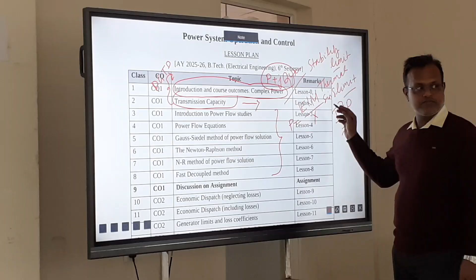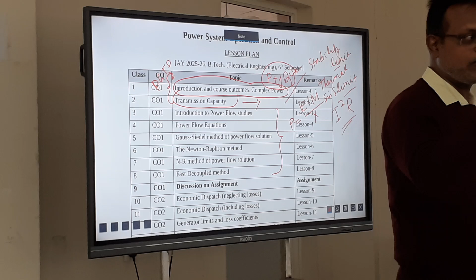Okay. So for a transmission line, it will be V1 V2 by X sin delta. So delta can be at most 90 degrees. So in that case, the transmission capacity of a transmission line is simply V1 V2 by X. So if you want to increase the capacity of the transmission line, you have to reduce the reactance.